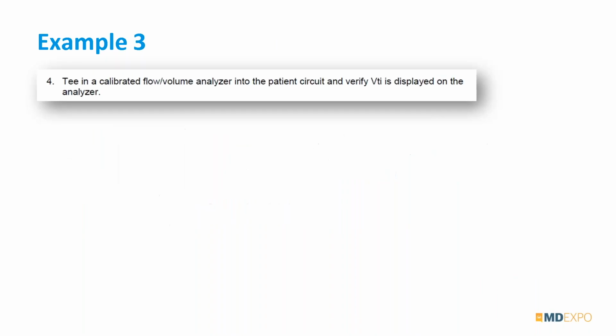In our third example, they just basically say, hey, tee in your analyzer and measure, in this case, VTI, which is inspiratory tidal volume. And they don't really give you a lot of guidance. So we see this all the time. You may only have one piece of flow analyzer test equipment, and you might have to use it on a whole myriad of ventilators or anesthesia machines. And the setups for each one can be different. So it's important that you know your device.